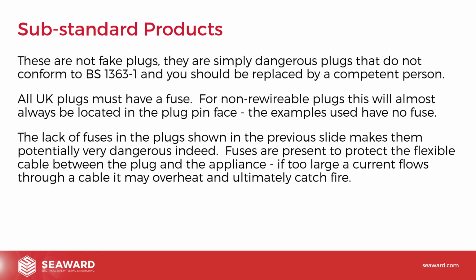Now, again, I would always say, if you see plugs like that and you think, all right, I'm going to rewire it, I'm going to put another plug on, just be careful, because if the plug's that bad, is the cable actually counterfeit? Is the cable substandard? Most times when you actually cut these things off, you'll see that the cable is very thin. It's not pure copper. It's the wrong colours. It's the wrong cross-sectional area. So again, sometimes it's not quite as easy as just changing the plug.